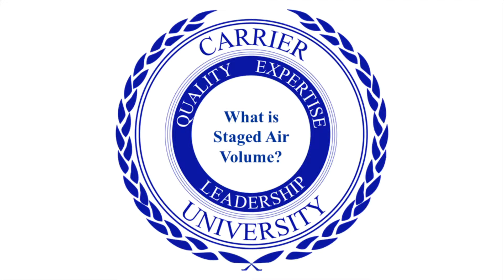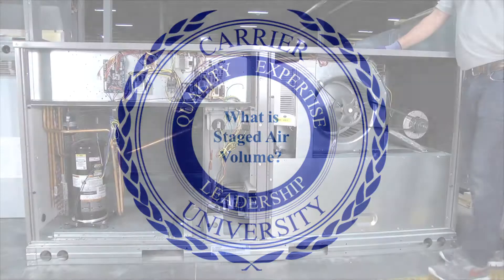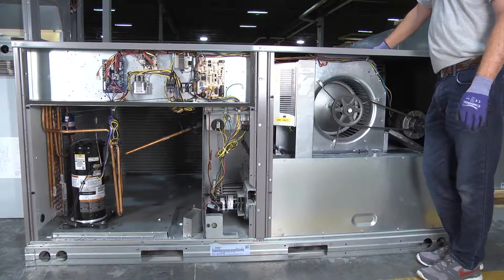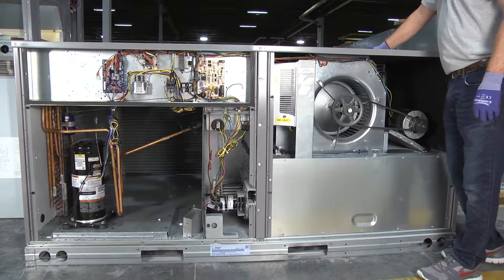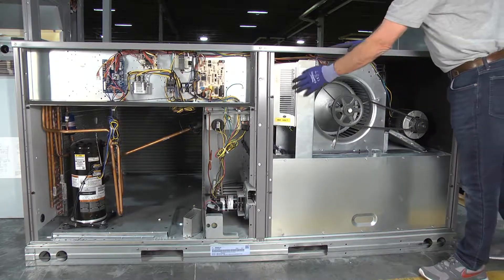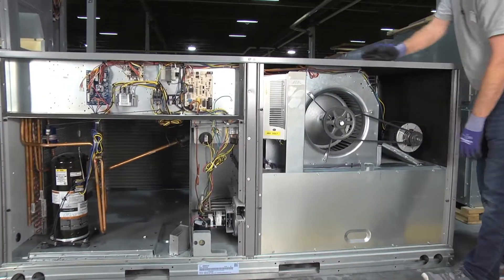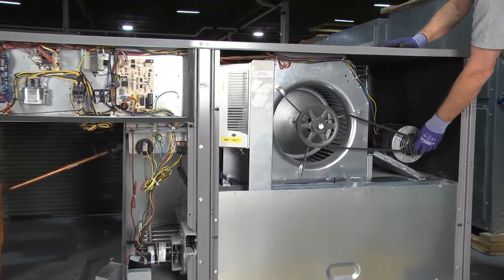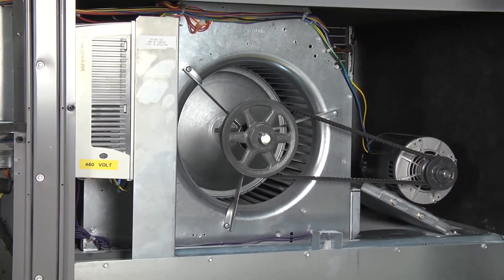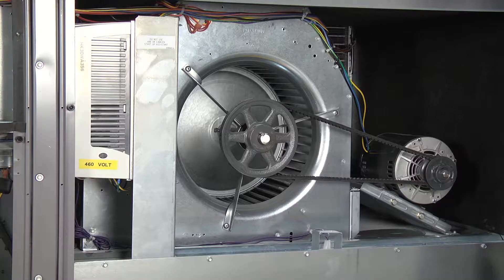Today we are going to talk about Staged Air Volume, or SAV units, and what's the difference between a Staged Air Volume unit and a typical rooftop unit. The Staged Air Volume unit is going to have a VFD, or Variable Frequency Drive. The VFD will control the blower motor to two distinctive speeds: a low speed for ventilation and first stage cooling, and a high speed for heat and second stage cooling. This is pre-configured at the factory.